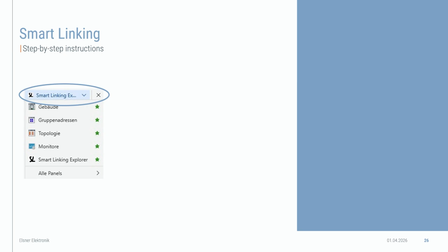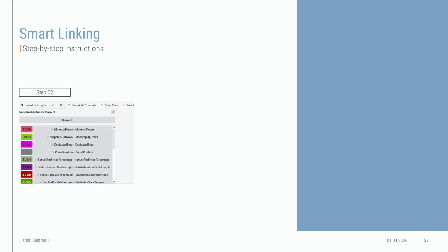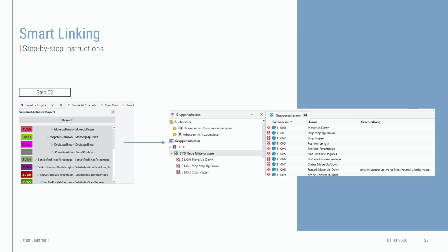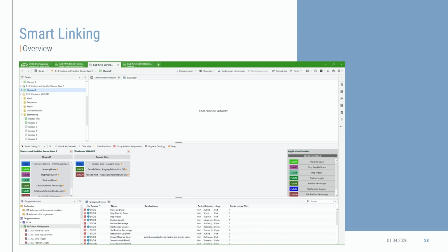We prepared a little demonstration of what you can actually do with the Smart Linking controller. The first step is you take the entire channel from the weather station or from the actuator, for example, and pull it into the Smart Linking Explorer. Just via drag and drop, it's very simple. In the next step, you take the other channel and connect it, and the result is fully automated, created group addresses. So first we pull down channel 1, next we pull down the channel of the facade, and then they will be connected to the group addresses.